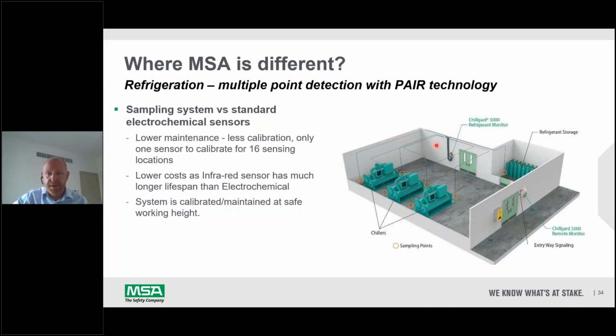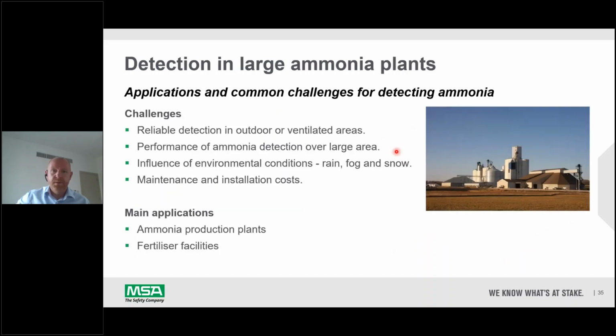For the ammonia applications, because the sensors are installed at height, it's much better to use a sampling system, because the sensor is installed at head height, where the sample is taken from the ceiling. So this is the other example of ammonia. It's mostly ammonia production, where we need to protect the boundary of the ammonia facilities. They're large facilities, and they want to know if there's a leak in a large area.